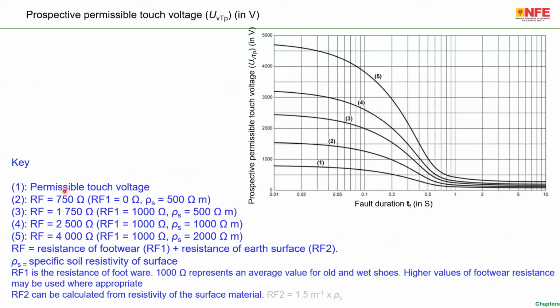Figure number 2 explains RF. RF is the resistance of the footwear. Let's say you have a small footwear, 750 ohm. In that case, the permissible touch voltage is higher. If your shoes have a higher resistance, then in figure number 3 the permissible touch voltage is even higher. If you have very good shoes and very good gloves, then you see that the permissible touch voltages are higher.